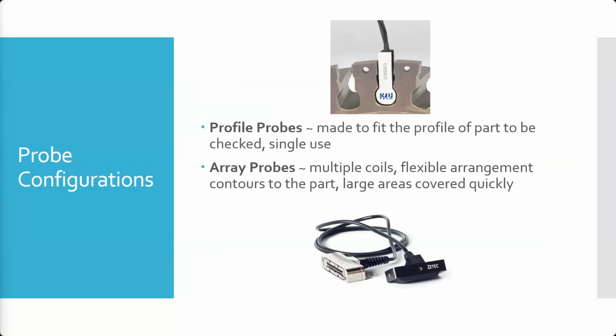Below is something called an array probe. Array probes have multiple coils. They come in all kinds of arrangements. Some of them are even like this one right here on the right, or this end on here, that's the plug for it. But the end here actually has a pad on the bottom of it. It's a squishy surface where you can push it against an irregular surface. And these can scan a wider area.